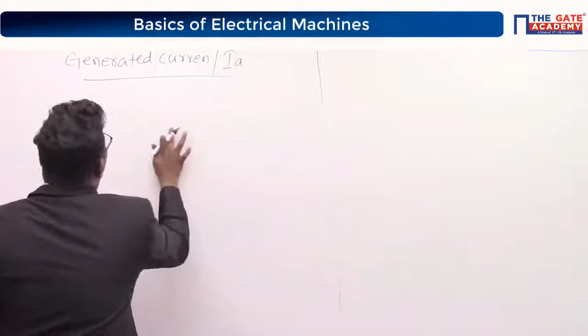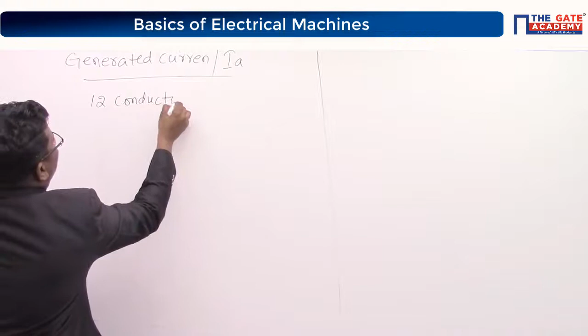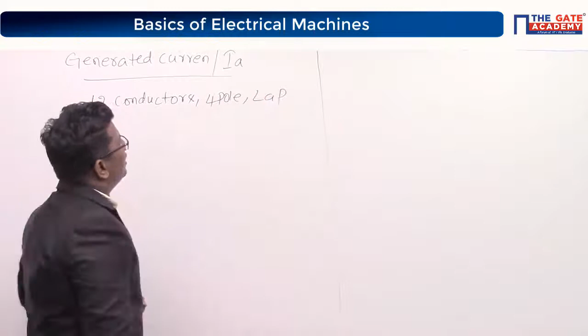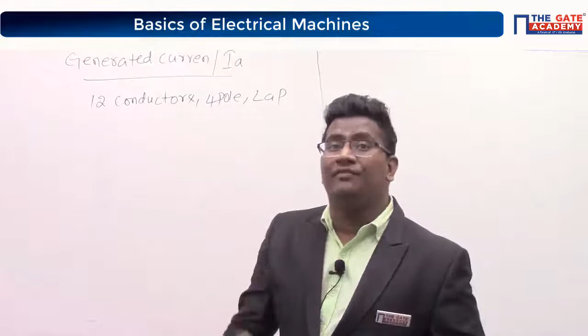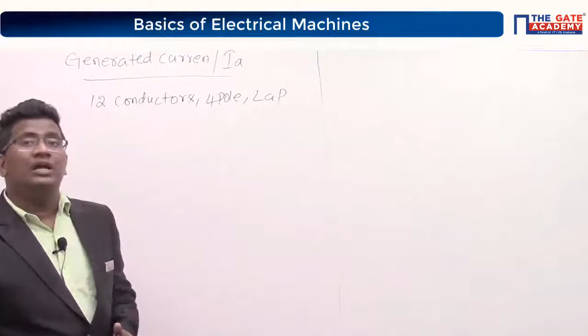Generated current or armature current, IA. You can use either the word generated current or armature current. Okay? Listen, same example: I will take 12 conductors, 4 pole lap winding. Tell me, 12 conductors, 4 pole lap winding, how many parallel paths do we have? 12 conductors, 4 poles, lap winding: 4 parallel paths.